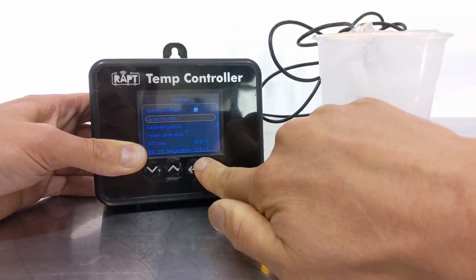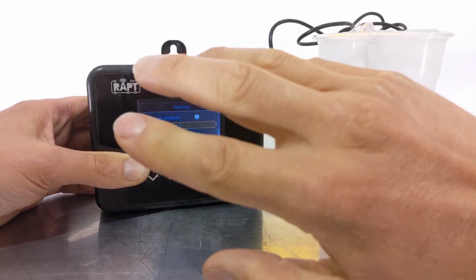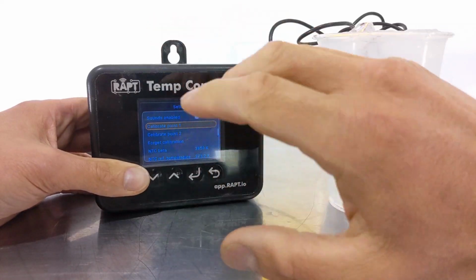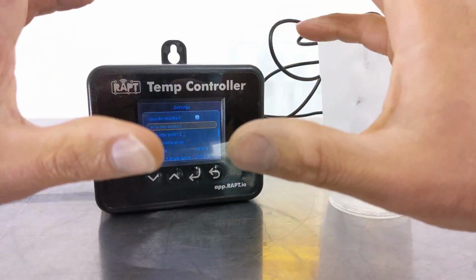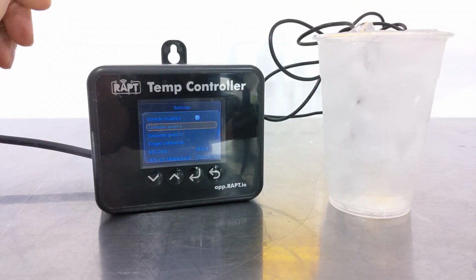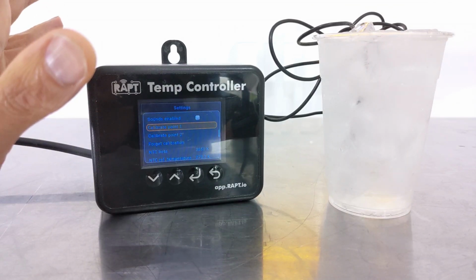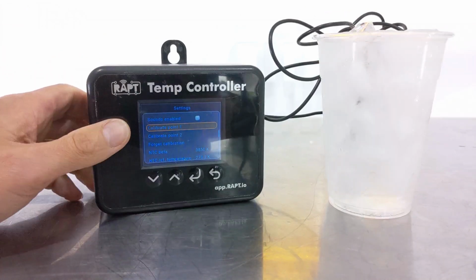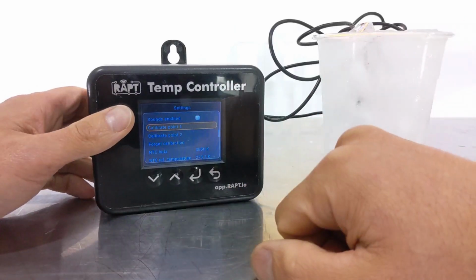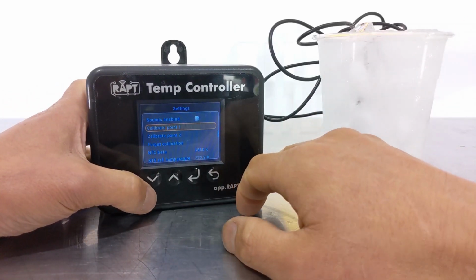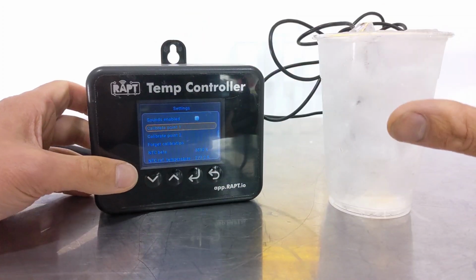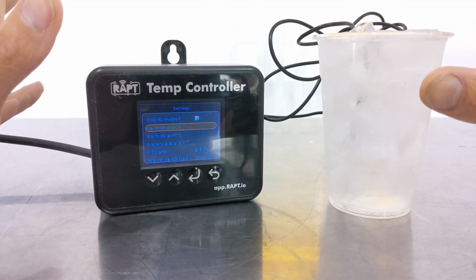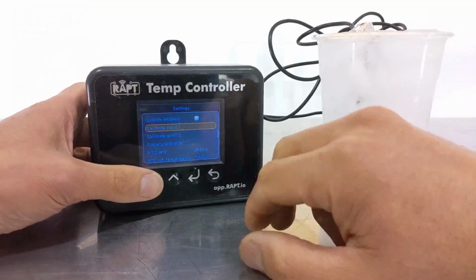Now, because I've only saved that one point, it can only basically save that as an offset. To really work out the complete graph and either stretch the graph in the X or Y direction, what you really need to do is put the second calibration point in. So at the moment, it's just an offset. A simple level of calibration will make it more accurate simply by putting one point in.